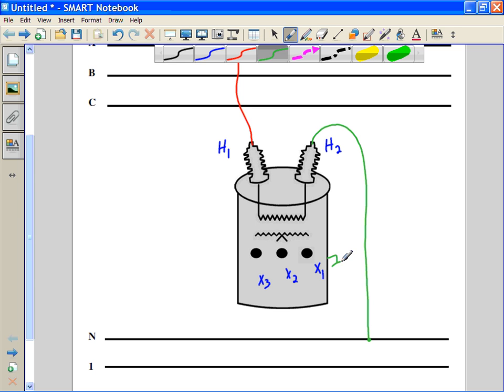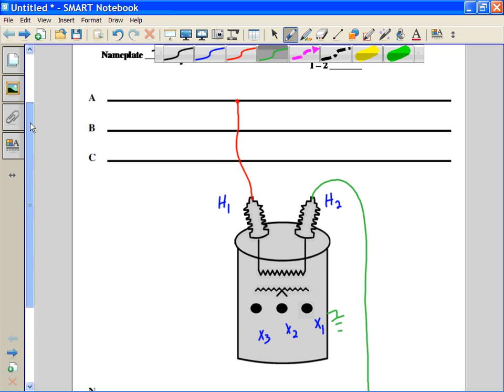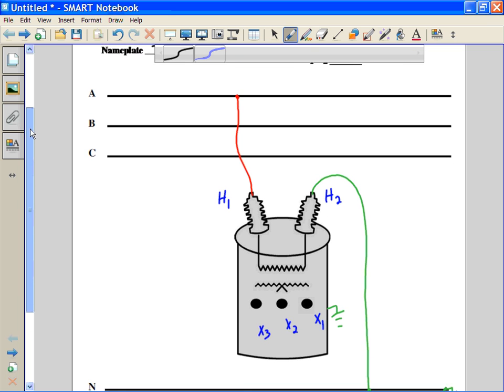We need to make sure that we ground our transformer case, and that we make sure that we show that the neutral is grounded as well. The neutral is in the secondary position, but it will serve as both the primary neutral and the secondary neutral on this particular drawing.